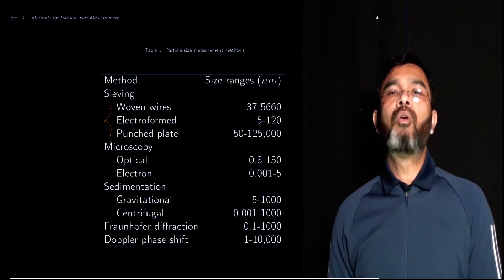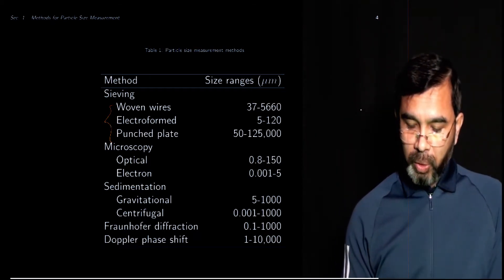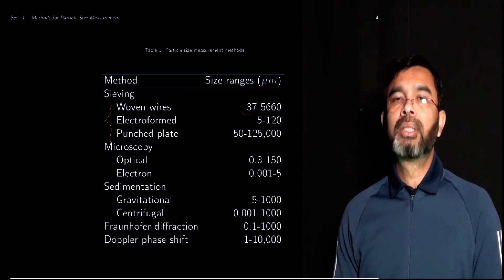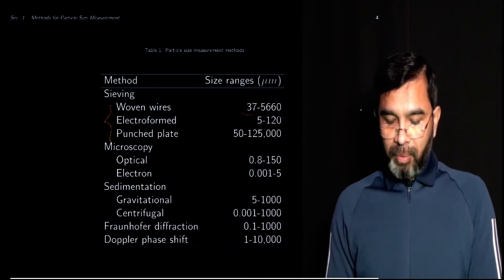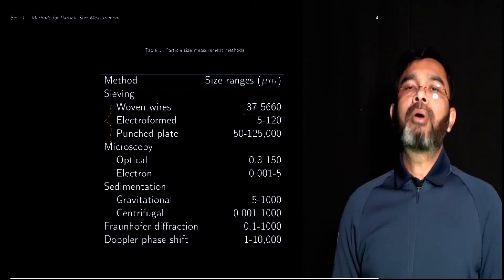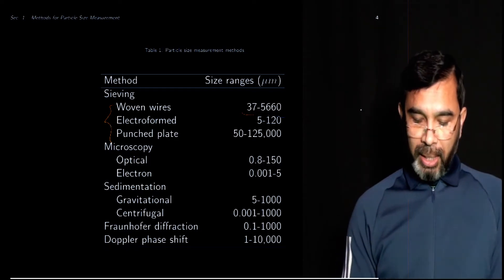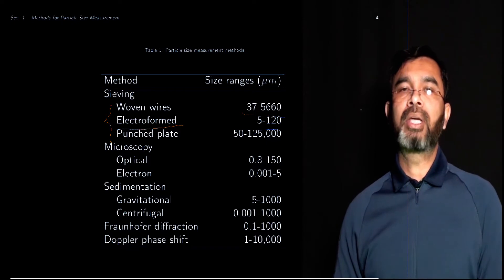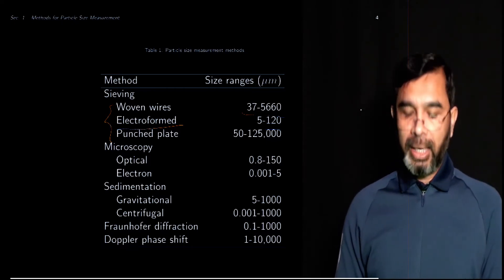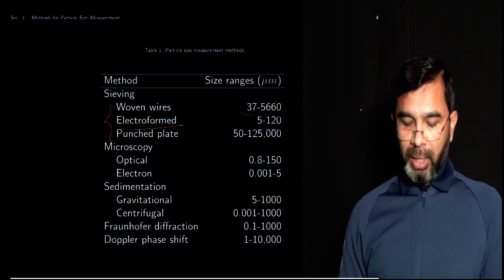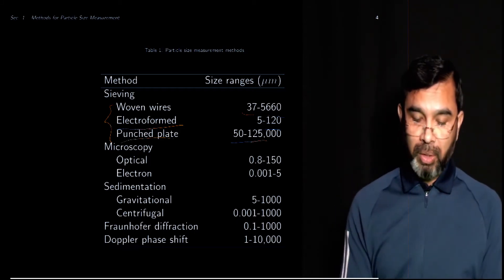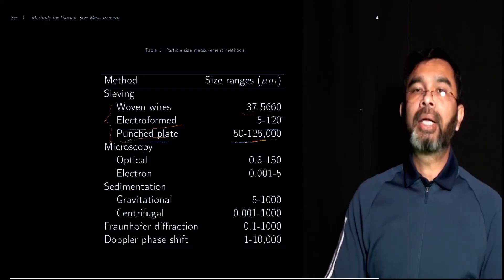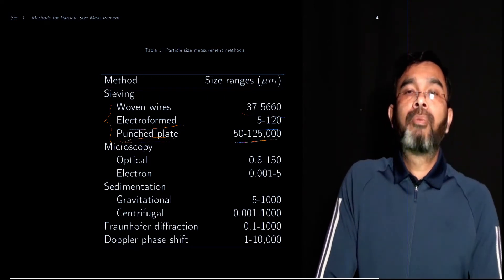For example, woven wires are used to measure particles between 37 microns and over 5 millimeters. There are other types of screens, such as electroformed, which is used to measure typically small particles between 5 and 120 microns. There are punched plates, which are used to measure large particles from 50 microns to around 125 millimeters, which is 12.5 centimeters. Those are mainly used in the mining industry where large particles or large rocks are involved.